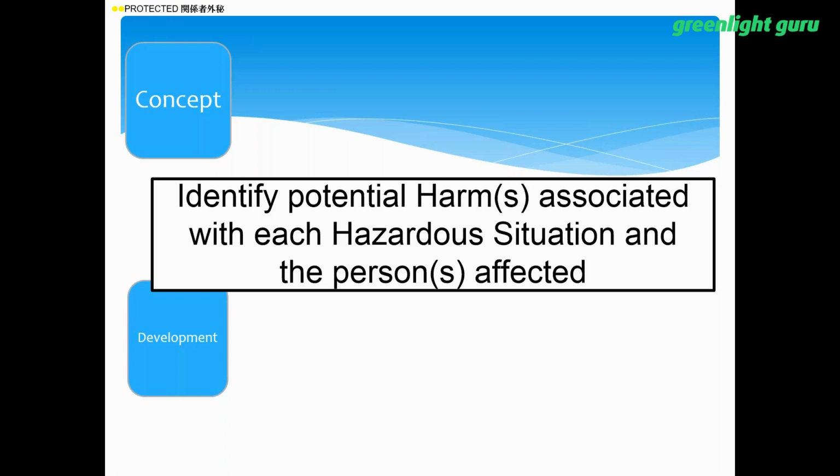And it's not unusual to have a single hazardous outcome result in a harm that goes anywhere from an S0 to an S5, because depending on how that hazardous situation manifests itself into harm, that could go, again, that entire gamut. And sometimes I've seen that noted in the risk management file where you have one hazardous situation that can manifest itself into several levels of harm depending on how it manifests itself.